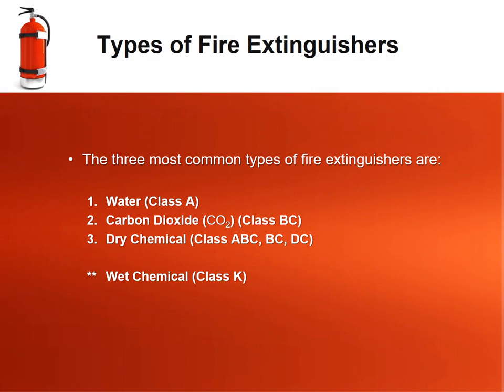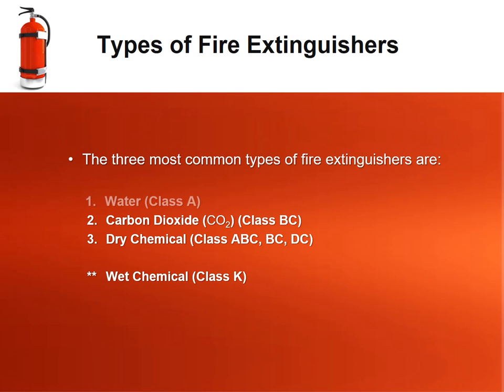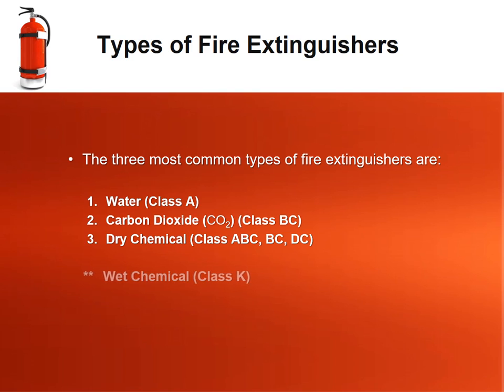Different types of fire extinguishers are designed to fight different classes of fires. The three most common types are: the water class A extinguisher, carbon dioxide extinguishers which are CO2 class B and C, and dry chemical class A, B, and C — which is the kind used most here at WC Striegel. There is also a newer class called the wet chemical fire extinguisher class K, which is designed to fight commercial kitchen grease fires.